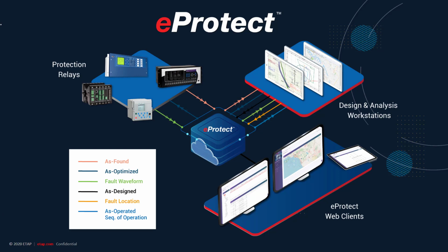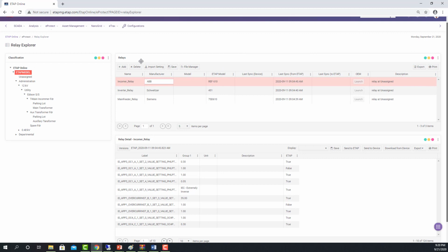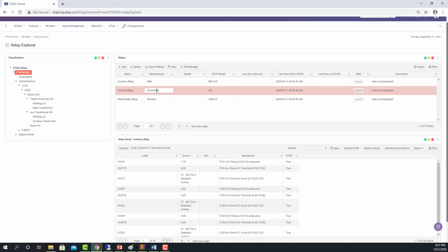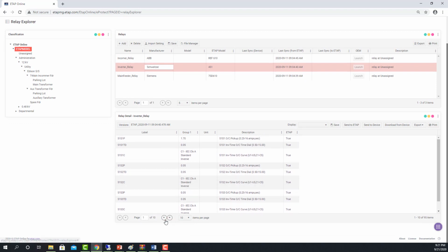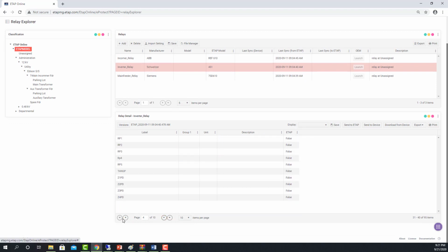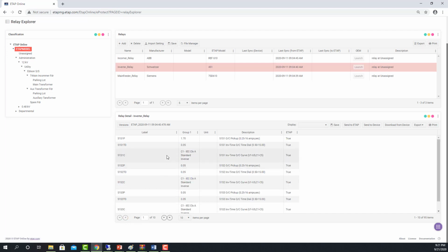So let's look at that interface. Here we have, for example, 3 relays configured in this substation. You can communicate to other relays and devices from other substations as desired, if you have the right permissions to do that. So in this case, we're looking at the 3 different relays. As you can see, as I click into the different relays, this information here is the different relay settings that were downloaded from the actual device.